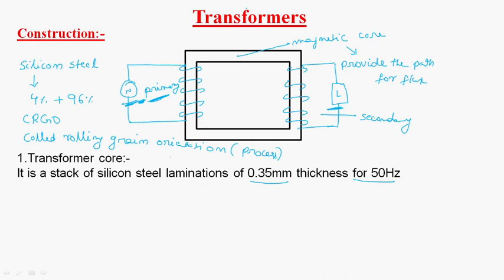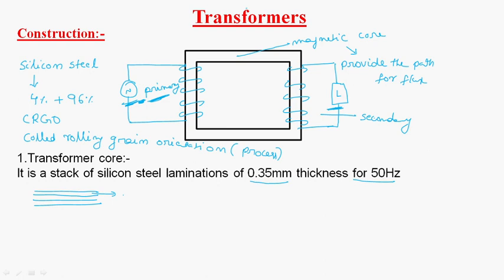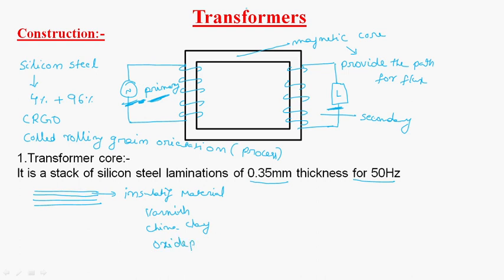This CRGO steel material is taken and made into laminations. A solid core is taken and cut into slices — those are laminations. Each lamination is separated with an insulating material such as varnish, china clay, or oxide paint — generally called red oxide paint.